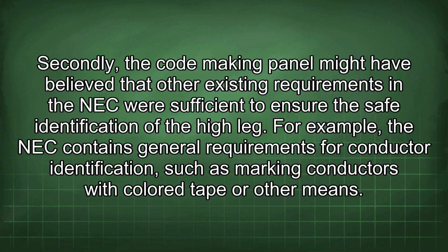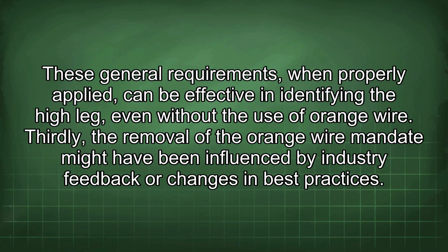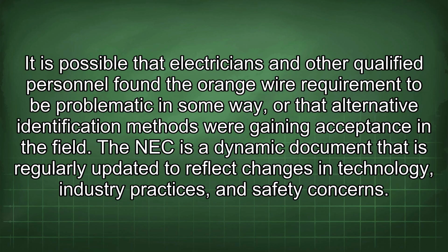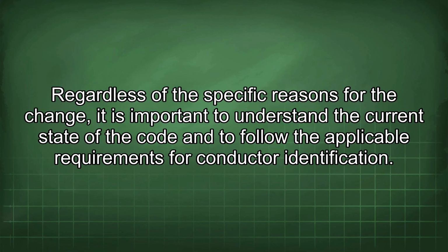For example, the NEC contains general requirements for conductor identification, such as marking conductors with color tape or other means. These general requirements, when properly applied, can be effective in identifying the high leg even without the use of orange wire. Thirdly, the removal of the orange wire mandate might have been influenced by industry feedback or changes in best practices. It is possible that electricians and other qualified personnel found the orange wire requirement to be problematic in some way, or that alternative identification methods were gaining acceptance in the field. The NEC is a dynamic document that is regularly updated to reflect changes in technology, industry practices, and safety concerns. Regardless of the specific reasons for the change, it is important to understand the current state of the code and to follow the applicable requirements for conductor identification.